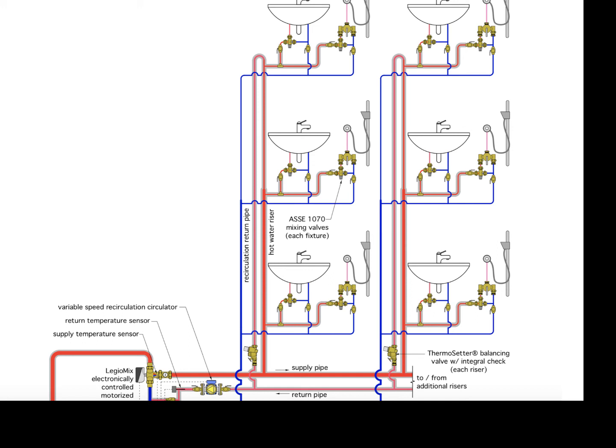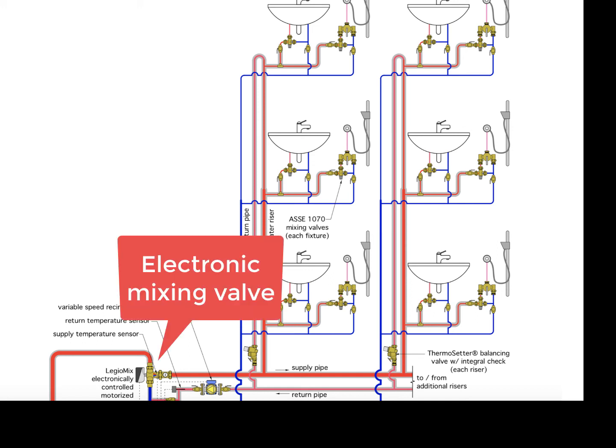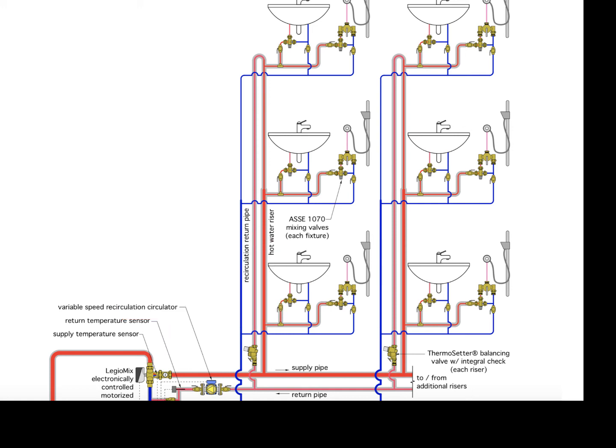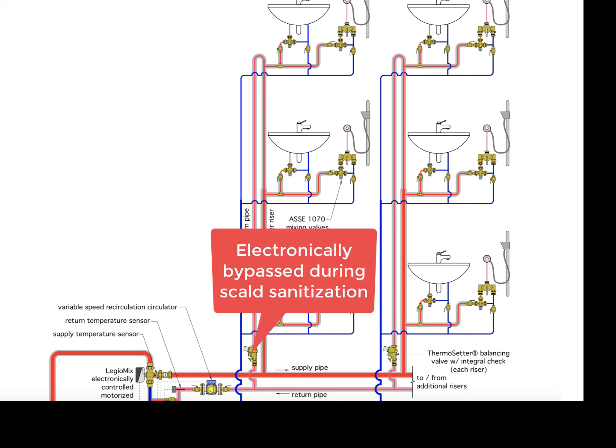In this drawing, a LegioMix valve is being used, which can be overridden during the scald sanitization cycle and allow the hottest water available from the storage tank to be circulated through the hot water supply mains, as well as the circulation return lines. And again, the Series 116 valve must have the electronic operator on it, which would be actuated to allow that hottest water to freely circulate through the circulation return lines and not be restricted by the thermal element.